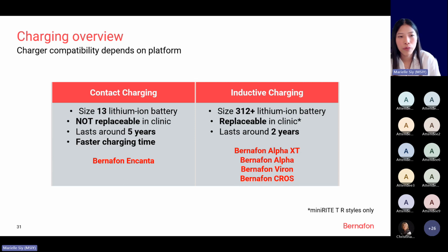years. And then on the right, you will see inductive charging. And for those who are not familiar with how this technology works, they use transmitting coils: a transmitting coil in the charger and receiving coils in the hearing aid. So when you put the hearing aid in the charger, the hearing aid's receiving coil is positioned very close to the charger's transmitting coil. And this allows an electromagnetic field between them and allows electric energy to be transferred from the charger to the hearing aid. So this technology is used for Alpha XT, Alpha, Viron, and the CROS instrument.